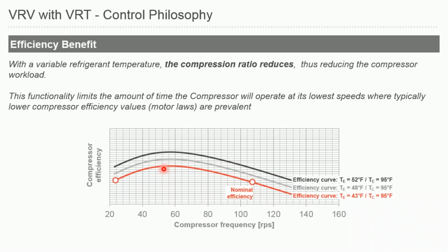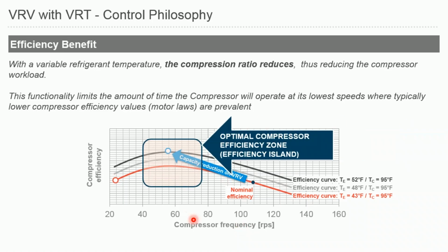But when you look at this example, you're seeing that below 50, 55 RPS levels, if you continue to reduce your compressor speed, you will be seeing less efficiency out of your compressor curve. So what VRT is doing is basically changing these different target evaporating and condensing temperatures. When you do that, you're basically changing your compressor curve as well, and the system always tries to stay in this efficiency island, as we call it, the optimal compressor efficiency zone. So it always tries to stay above this 50, 55 RPS level, the optimum compressor efficiency points, and it never tries to go down to these lesser efficiency levels below 50 RPS.